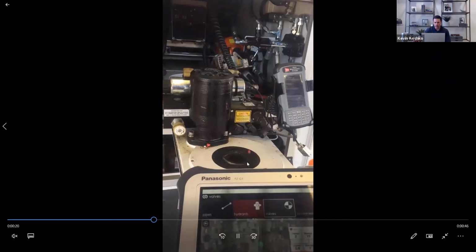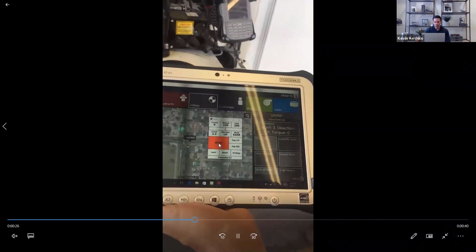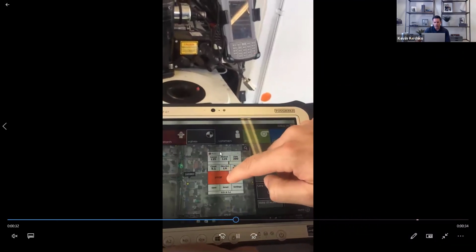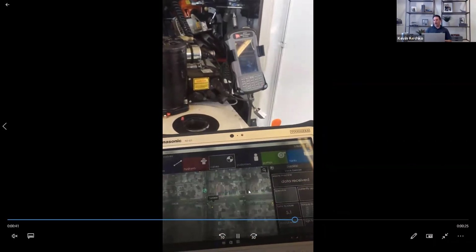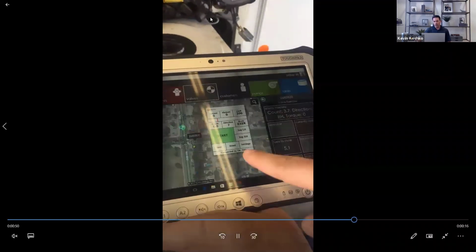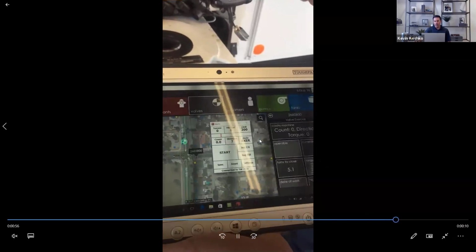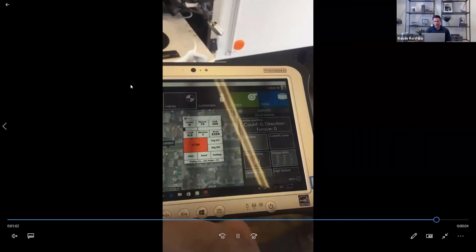So I think it's important to show you how it works in the real world. As it finds its set points, you can see on the right-hand side, the count and direction and torque, all of those values are getting updated as well. So just full control using a touch screen, and again, wirelessly connected. You can also see it already has that existing recon unit in there docked, it's not even being used in this case. And then here's that torque limit being adjusted. And then all that torque data and turns getting saved to the form itself, which is really nice.